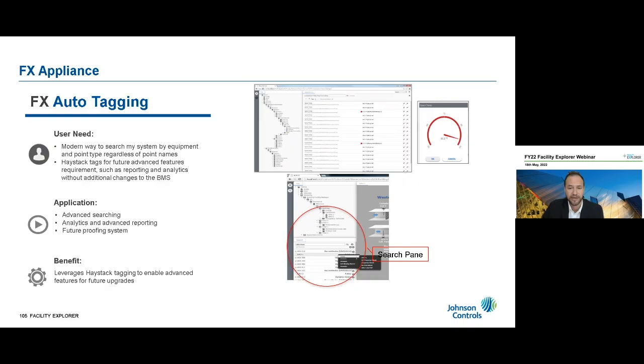What we did with FX auto tagging is add a full library of tags that are applied to the points and devices automatically. That's the key thing, that it's applied automatically. So when we use the import manager, we talked about earlier, we automatically add all the tags in that library to the imported points. The result is we have a fully tagged system without doing any additional work.